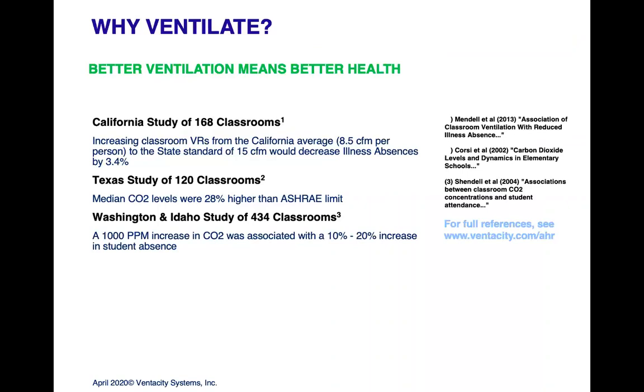Let's talk about ventilation and kind of put it in perspective of today's world. And we already knew, and I've already used some of these slides and some of these studies for several years, that we've been talking about it. So they've been studying classrooms and schools with ventilation. The first one there in California, what if we increase the ventilation rate from 8.5 CFM to 15 CFM per student, per person in the classroom? And they decreased illnesses by 3.4%. Obviously, better ventilation translates into healthier classrooms. I'm going to talk a little bit more about that.